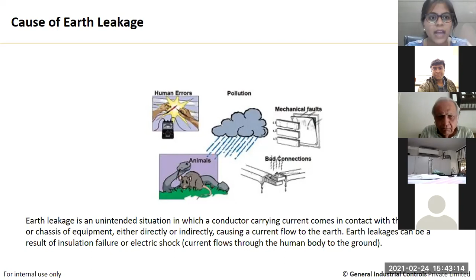Many accidents can happen. The same with pollution, and also mechanical fault. For example, suppose there is a motor on which we do a lot of maintenance, and someone hasn't fitted it well after maintenance, then there are some gaps, and the air in that gap gets ionized, and because of that the leakage current builds up, which is not good for the system or for the person. The same with animals. Suppose someone is working on a panel, and there can be some insects, let's say a rat or lizard, and it may damage the insulation of the conductor. So these are a few reasons why leakage happens.